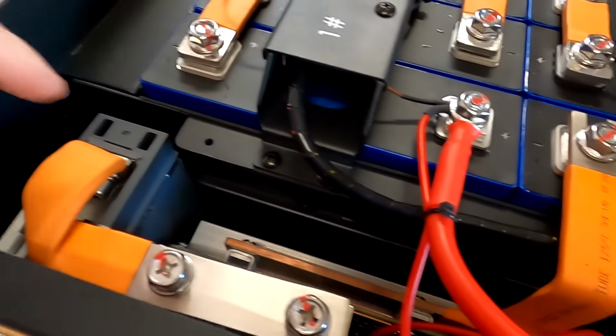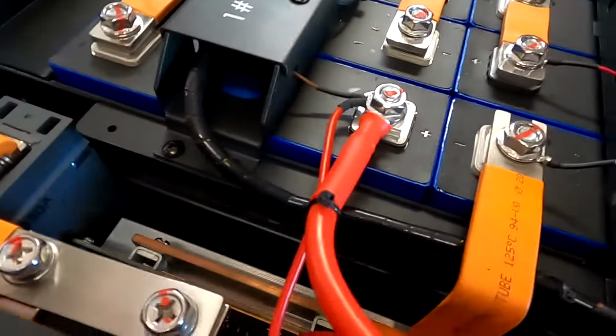6-gauge wire is a 16 square millimeter cable. It says it here around 72 amps. So this is a bit on the small side, I must say. I would rather see 2 of these cables here going from the positive to our circuit breaker bottom. It's a silicon cable, so they can carry a bit more current. But man, these Chinese batteries, they're always saving on the cable size.